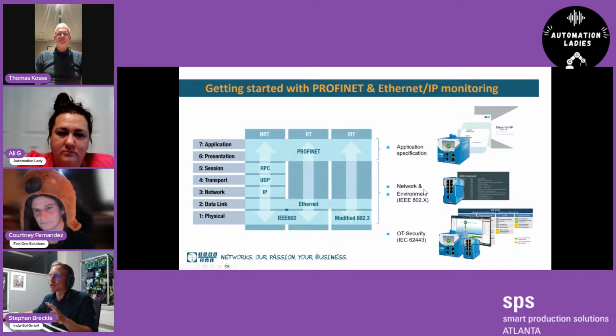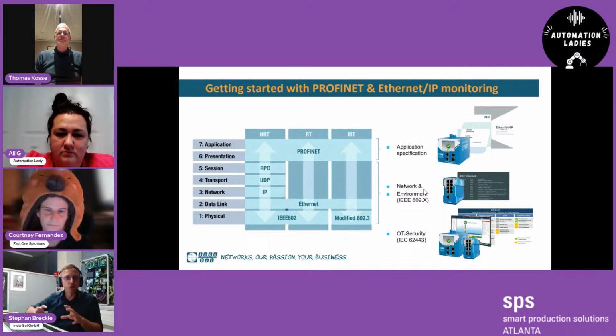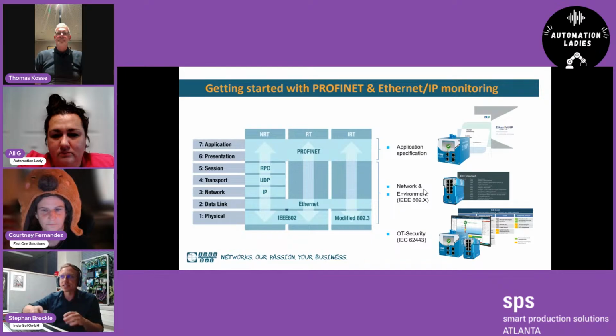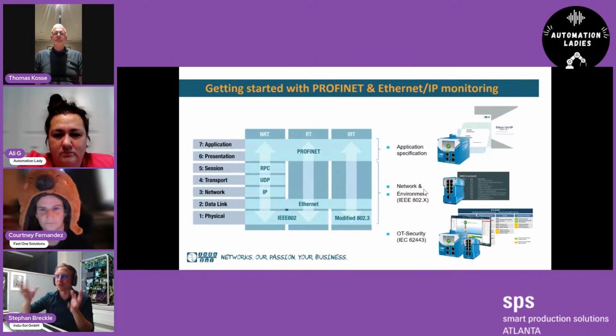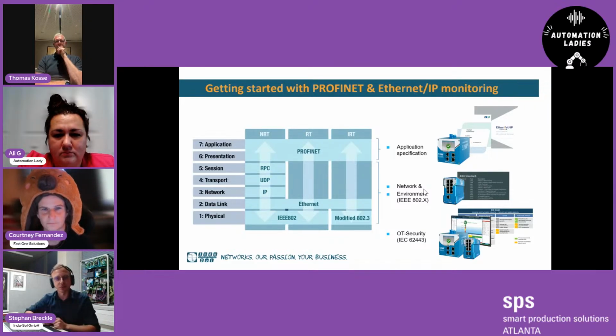First of all, your PROFINET, Modbus TCP, EtherCAT, or Ethernet IP is just the application that runs on IEEE Ethernet. If you think of EtherCAT - let's say, in this presentation, let us speak just over PROFINET and Ethernet IP, because those are very comparable and the standards are very close to each other. The basement is very, very close.